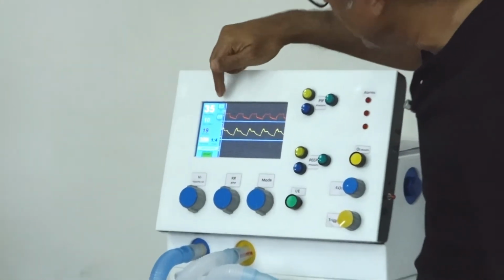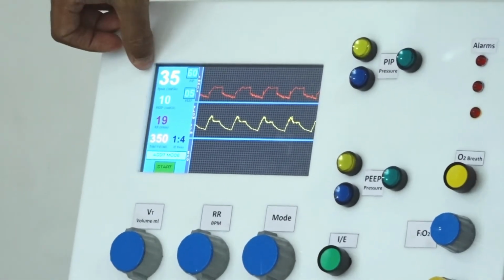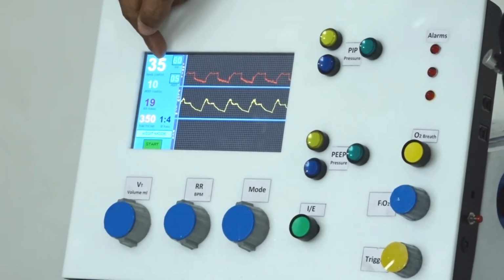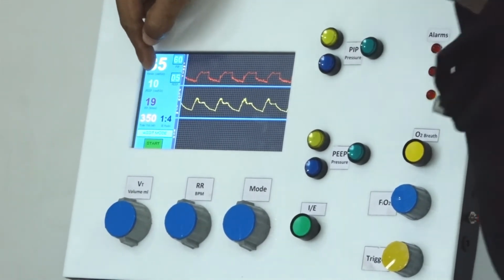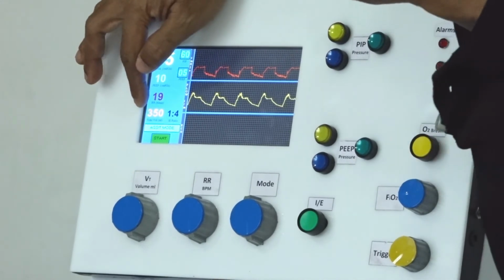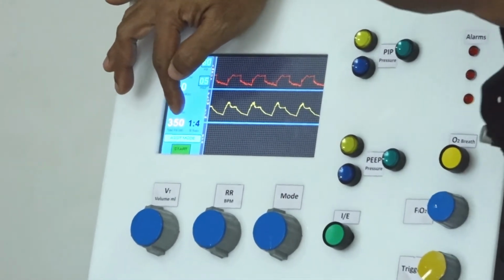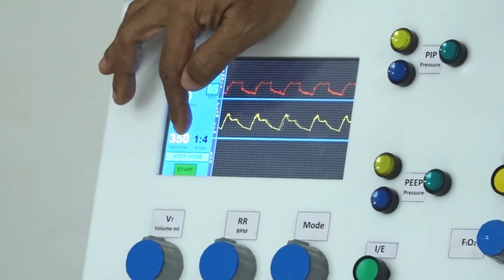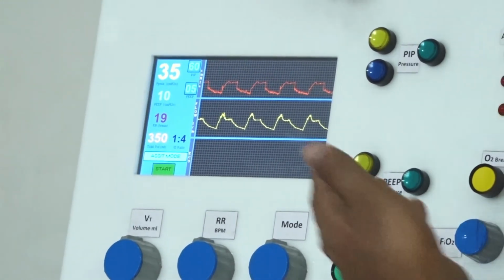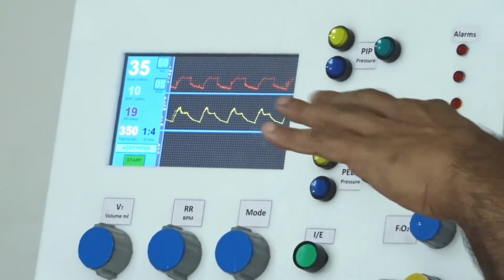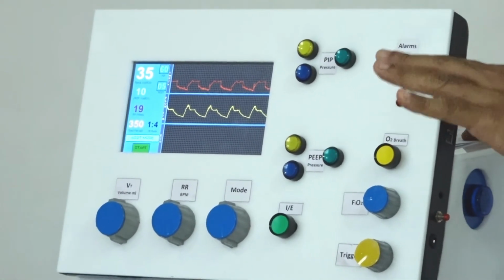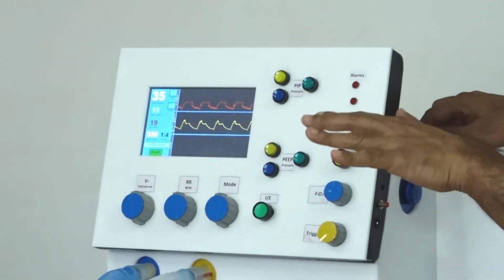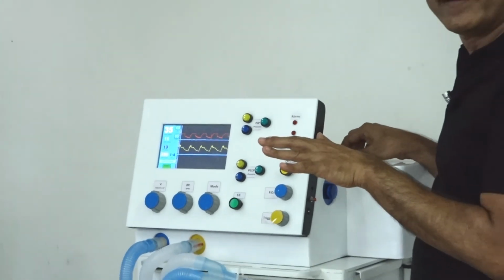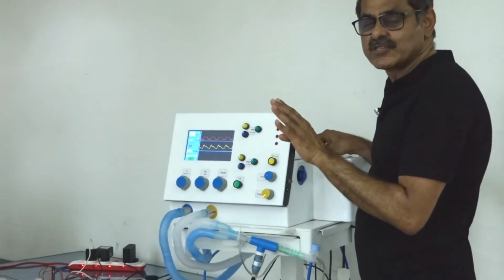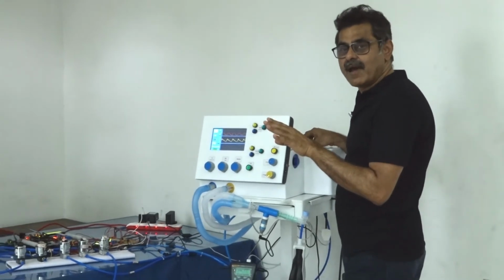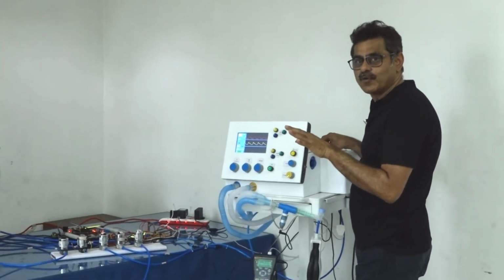Let's focus on the touch control screen here. This is the peak inspiratory pressure. This is the peak pressure, the tidal volume is set at 350, and the I:E ratio at 1:4. And of course, you can see the waveforms. So it is a low-cost ventilator which actually looks like a high-cost ventilator, and that is the ICoVent. It's a solution not only for India or Telangana, but for the whole world.